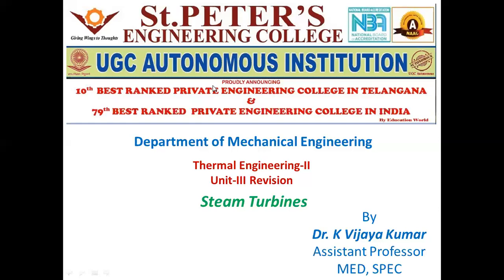If 1.2 to 2 bar is required, we choose the low pressure turbine, whereas up to 40 bar are the medium pressure turbines. Above 40 bar are the high pressure turbines. Next classification is according to the number of stages. Here the number of stages may be single stage or multi-stage turbines.